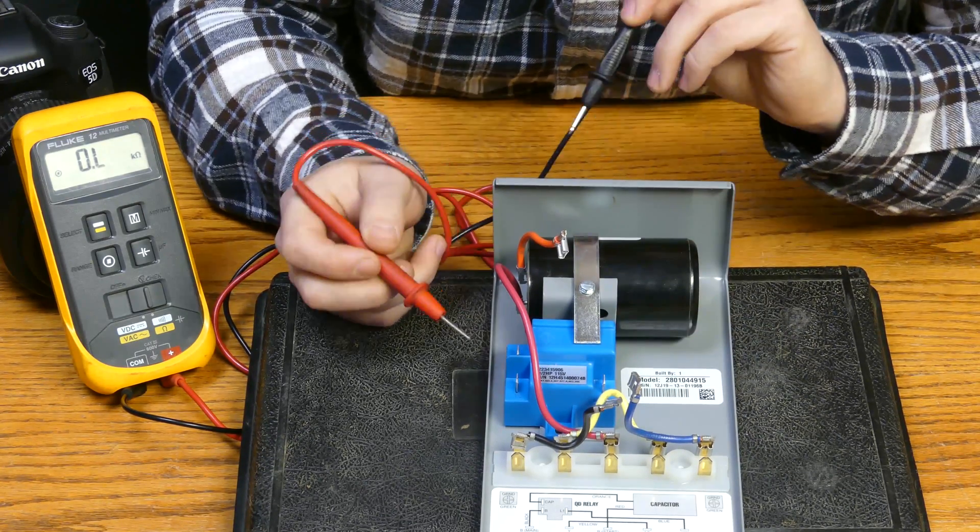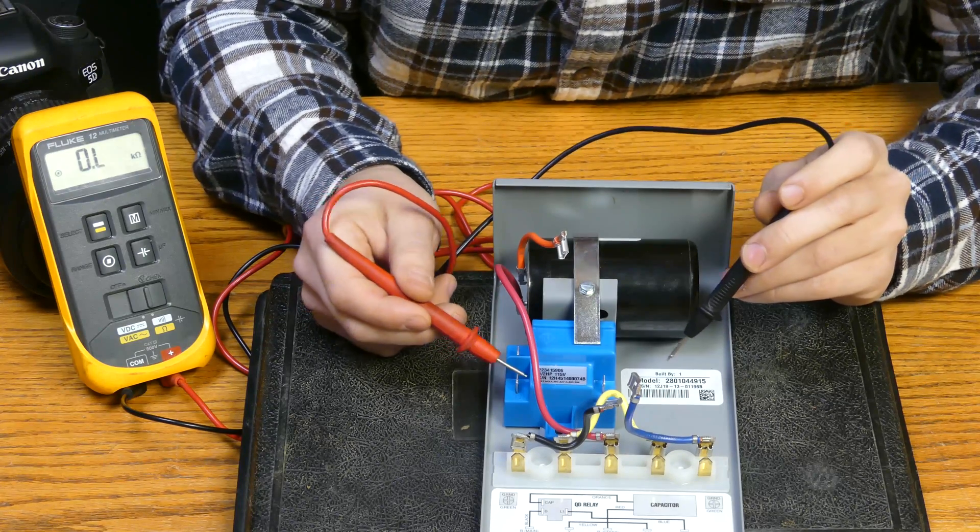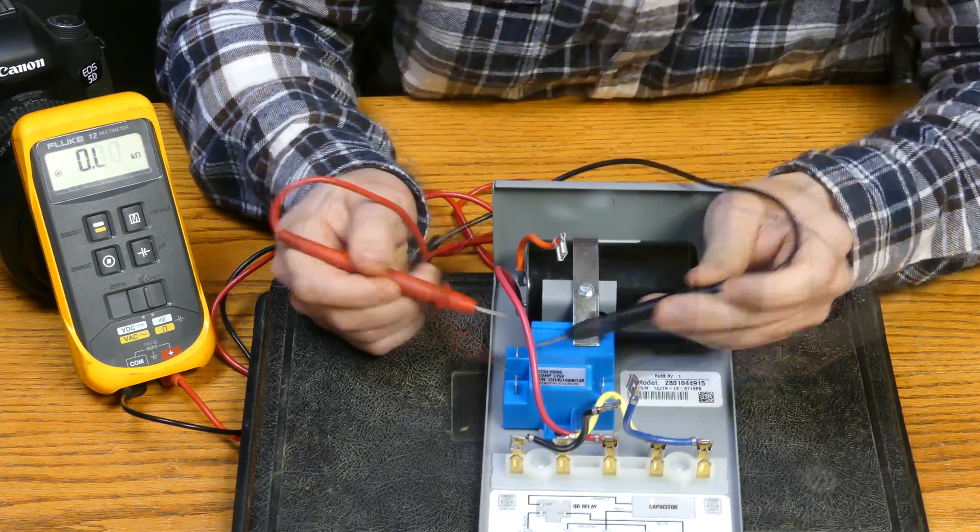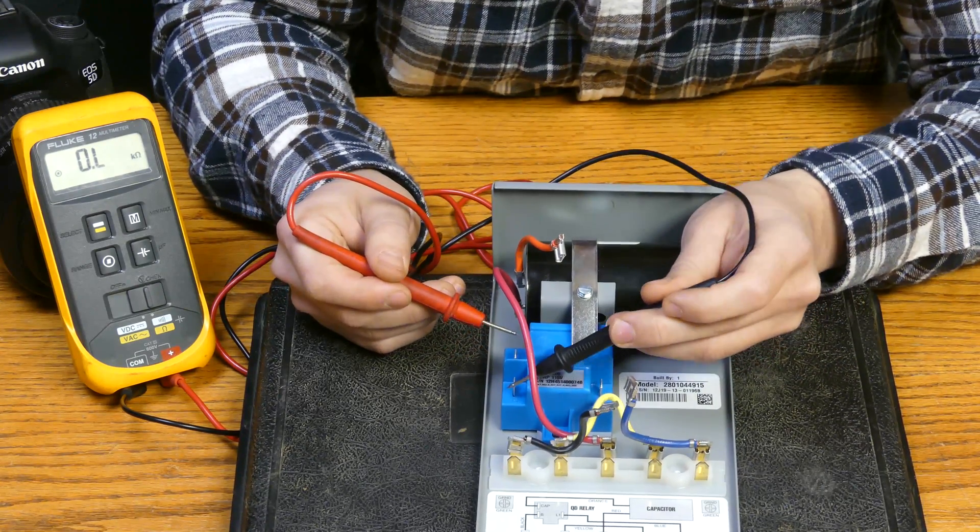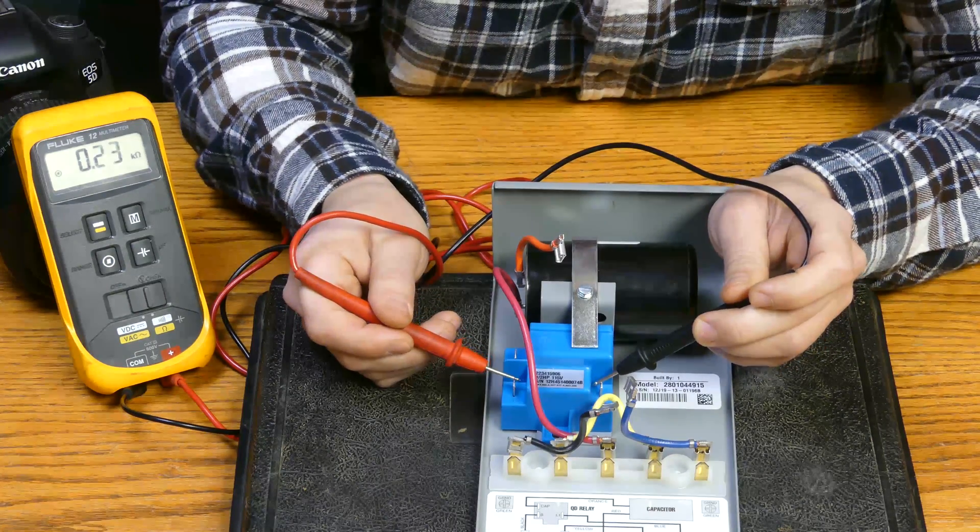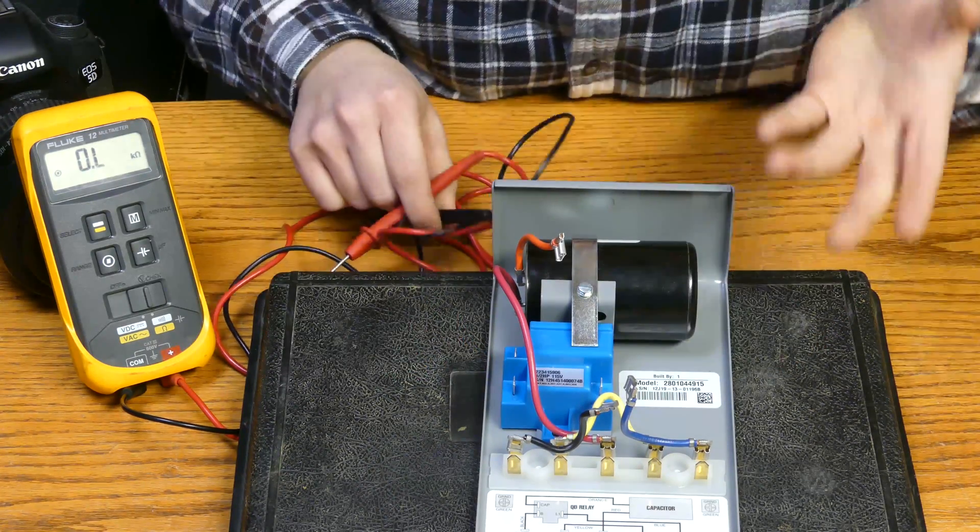Alright, and then the last one we're going to check here is going to be between B here and L1, and we're looking for 0. So just to recap again, nothing between B and cap, and then between B and L1, 0. So that relay is also good.